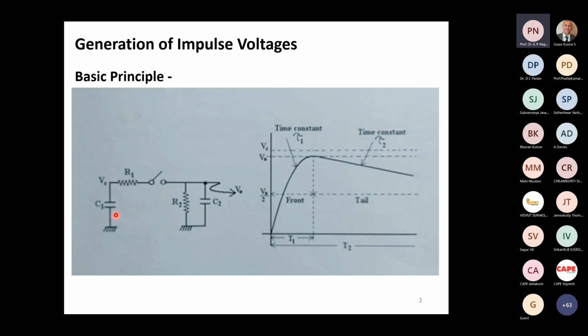The tail time is dictated mainly by C1, R1 plus R2. So we get a wave shape of this kind very easily in the laboratory today. Very, very easily we can do that. Typically you will see that R2 is much higher than R1. C1 is very much higher than C2 because front time is decided by R1 and C2. Since it's very small, R1 and C2 are very small. This tail time is dictated by C1 and R1 plus R2. Therefore, you will find that C1 and R2 in particular are very much large compared to the other resistances.